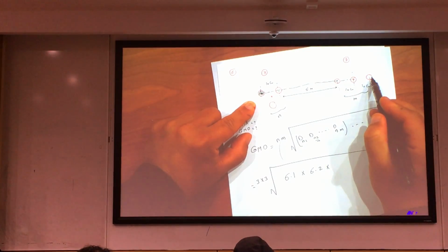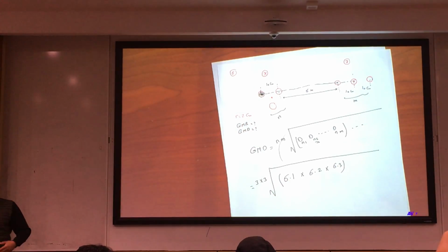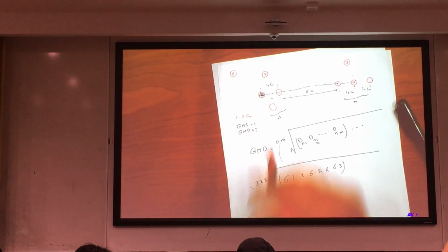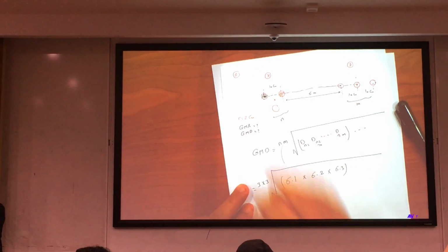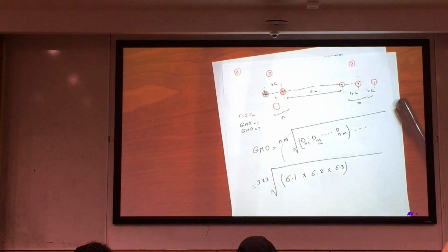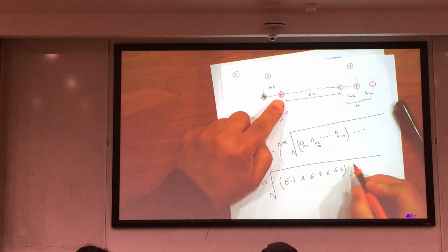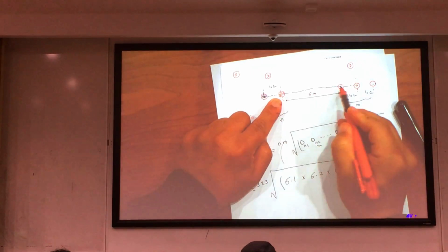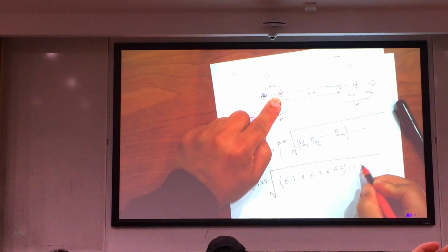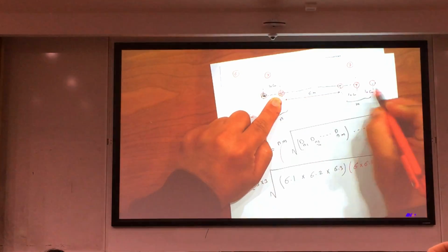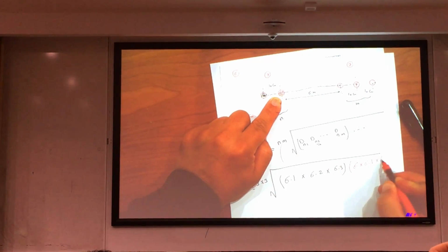And then between this conductor and the third conductor, 6.3. Finished with this conductor, take the other one, which is this one here. So again, multiply the distance from the center of this conductor to all other conductors in the other side. So this one will be multiplied, the distance between this one and the first one, which is 6 meters, multiplied by distance between this one and the second one, which is 6.1. Distance between this one and the third one, which will be 6.2.